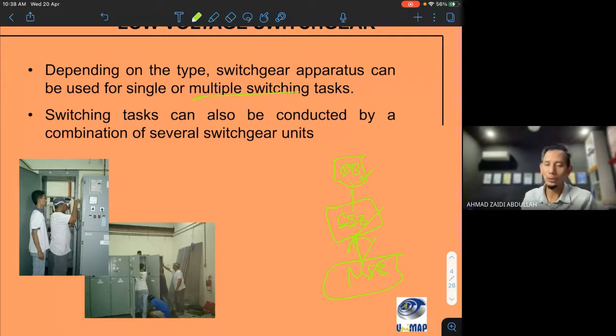Or multiple switching tasks, let's say this one trips, fault here, and then the rest also trip, you can set it. Tapi that condition is not so smart lah kan. We want to design that if there is a fault coming here, the rest of the DB still maintain, and then this SSB also can maintain performing. Because some of the designers don't design the correct way, so when a fault comes here, the whole building, the whole system is tripped. Okay.